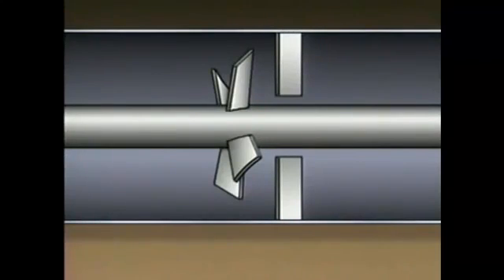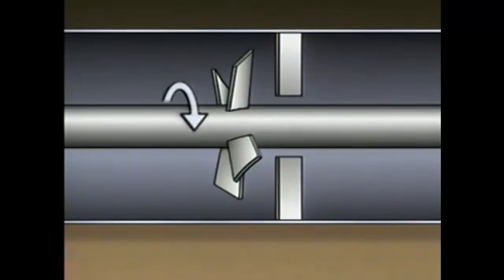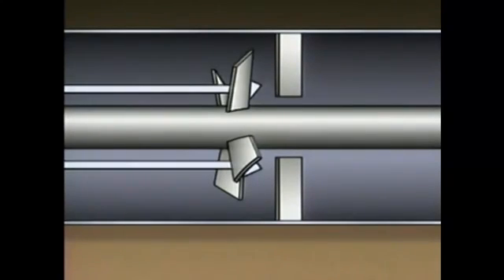As shown in this simplified illustration, the main internal components of an axial compressor are rotating blades, which are attached to a shaft, and stationary blades, which are mounted around the shaft. During operation, the rotating blades spin like the blades of a fan. They draw gas in and accelerate it to increase its velocity. The rotating blades then push the gas towards the stationary blades.